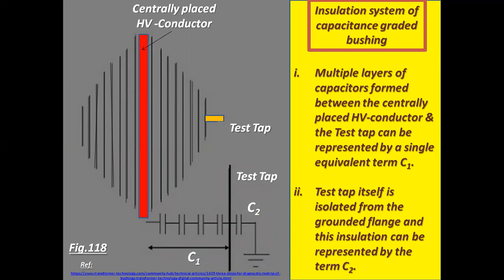The insulation system of a capacitance graded bushing, with multiple layers of capacitors formed between the centrally placed HV conductor and the test tap, can be represented by a single equivalent term C1. Number two, the test tap itself is isolated from the grounded flange, and this insulation can be represented by the term C2. One is from the centrally placed HV conductor to the test tap, another is from the test tap to the grounded flange.